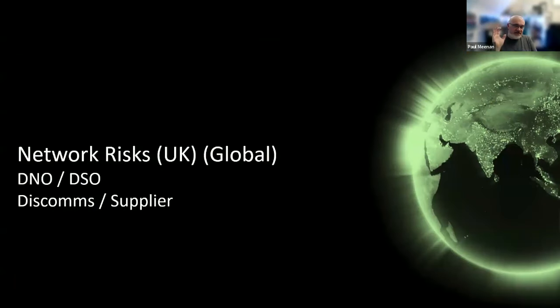So getting back to those images where we had that earth current, what could be wrong? What hidden mystery have we found now? The hidden mystery is the network risks, or what we call in England the DNO, distribution network operator, or the distribution system operator. I believe in India they're called the discoms or supplier. Again, feel free at the end to kick me if I am incorrect.